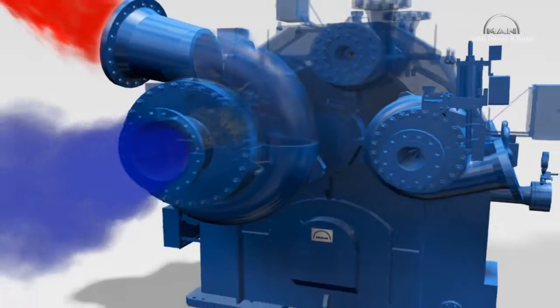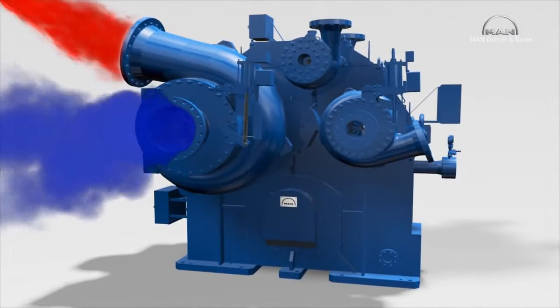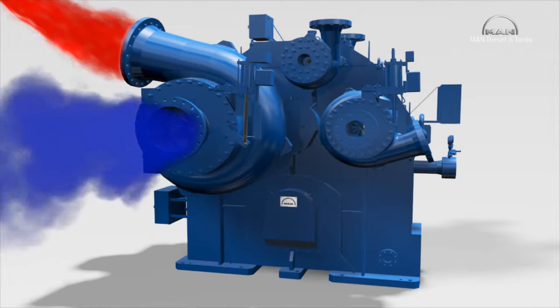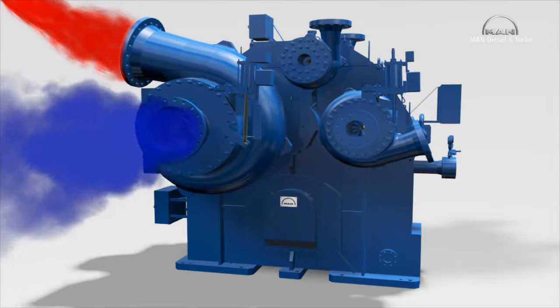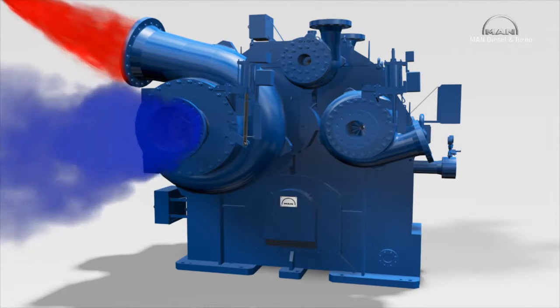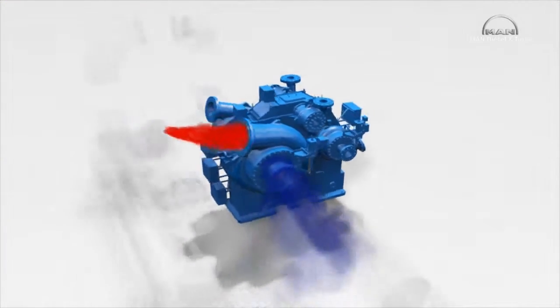With each compression, the gas temperature rises. This in turn somewhat reduces the density and increases the volume. Because this means that the following compression process would then require more energy, the gas flows after each stage through piping to an intercooler that reduces the gas temperature before the gas enters the next stage.